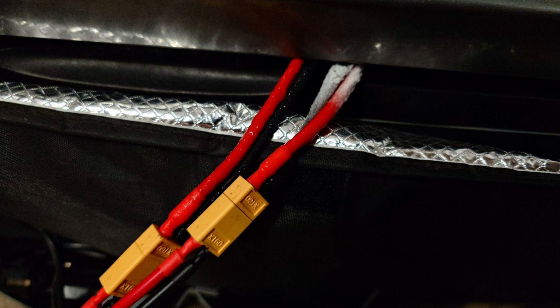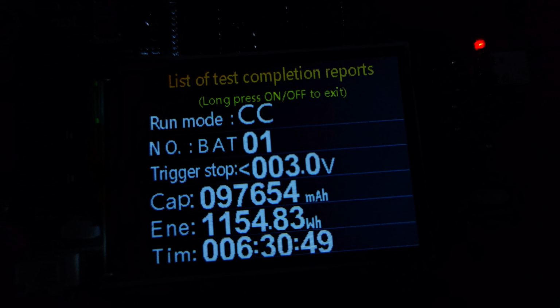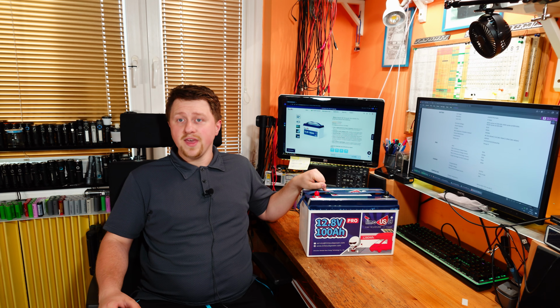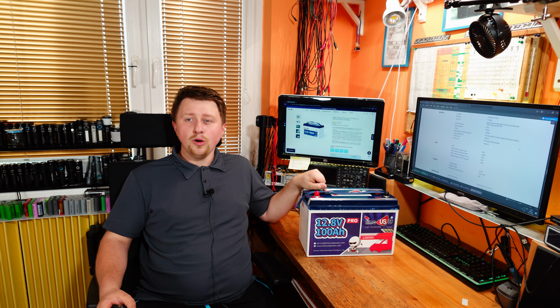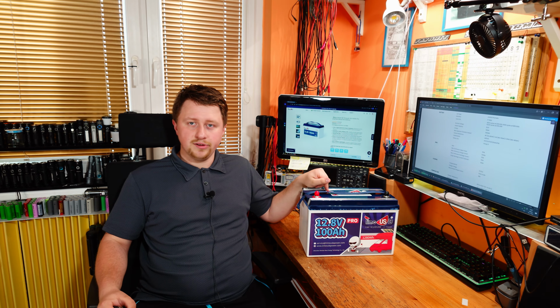Testing current was 10 amps. Measured capacity was 97.654 amp hours, and energy was 1154.83 watt hours - very close to the nominal, and actually beautiful. It has almost the nominal capacity, even when frozen to minus 20 degrees Celsius.